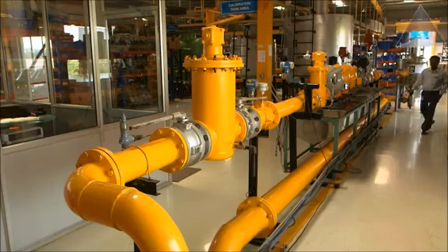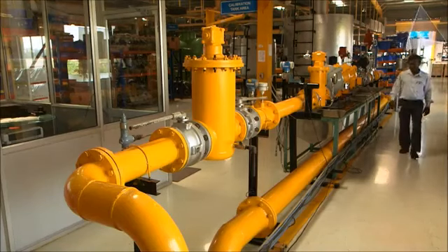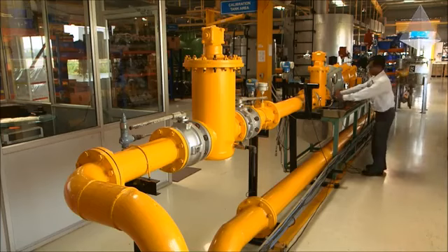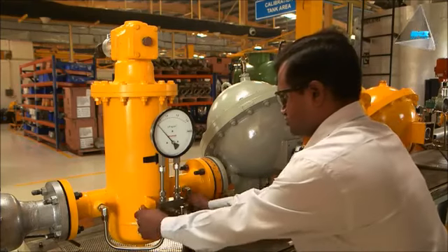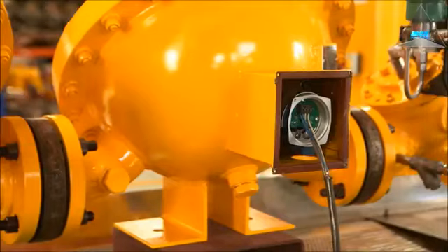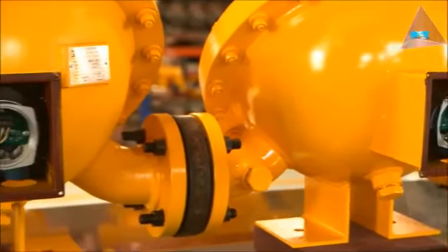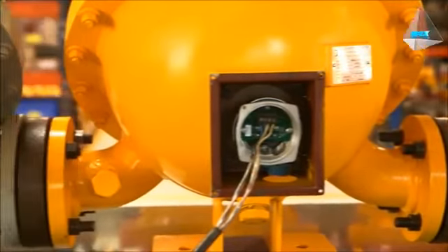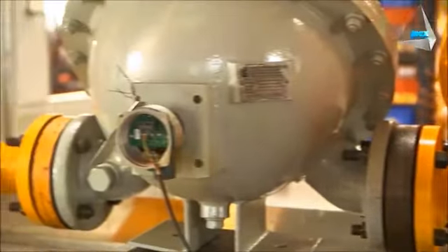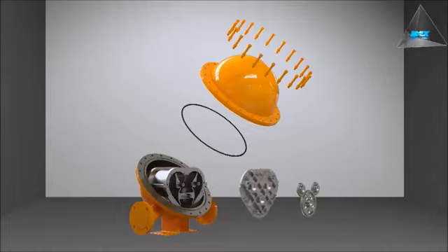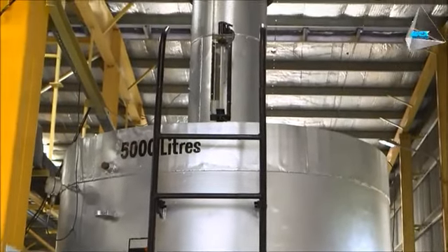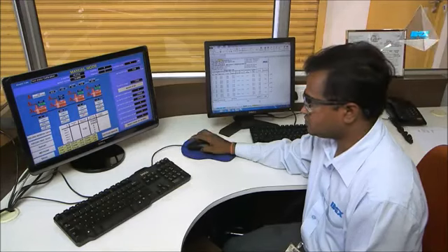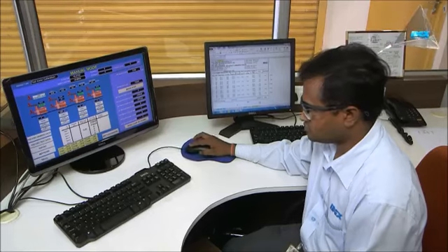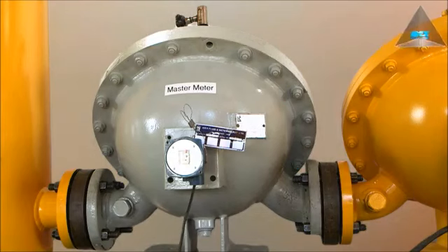All the meters will be tested for linearity and repeatability on the IDEX fluid and metering test bench against master meters, using Calibest L as a test medium at ambient temperature and a system pressure of 1 to 3 kilograms per square centimeter. The master meter is the reference meter, which has been proved against the IDEX fluid and metering 5 KL prover tank. The master meter proving data will contain the master meter K factor at different flow rates.